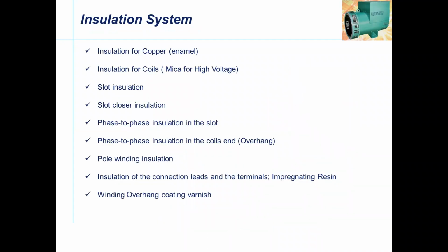Coming to the insulation system, the insulation for copper is very important. There is a dual coated insulation on the bare conductor of the copper, which is electrical grade, and insulation for the coils, mica for the high voltage machines. Slot insulation, which we'll discuss when the core has been built: there is a slot on the stamping, so slot insulation is given so that no short circuit happens to the body. And slot closer insulation, again, after the winding, we prepare one more insulation over the winding. And phase-to-phase insulation: this is an insulation given between the phases, that means R phase and Y phase or B phase, which you will be seeing in the next slide.